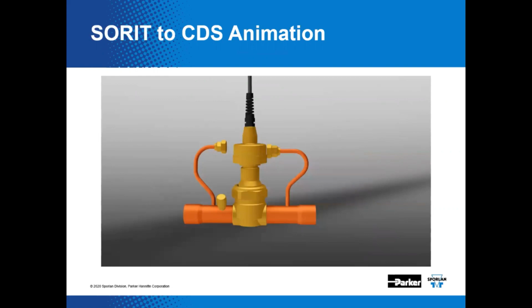But the body sleeve is removed and a number of other different parts are changed out, and then you wire the valve to a controller and run the sensors that are needed. And of course don't forget that you may need to consider some contamination protection, but installation of this is pretty straightforward. It's very straightforward. Yeah. If you wish, as we just demonstrated here, this conversion can be done without ever firing up a torch. That's true.